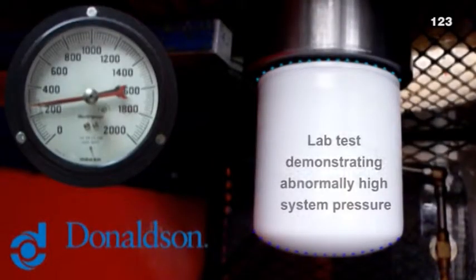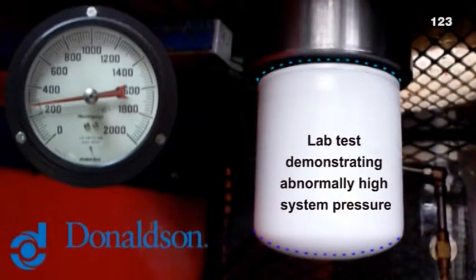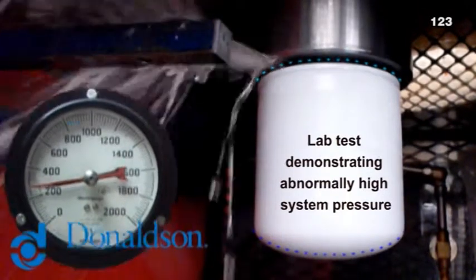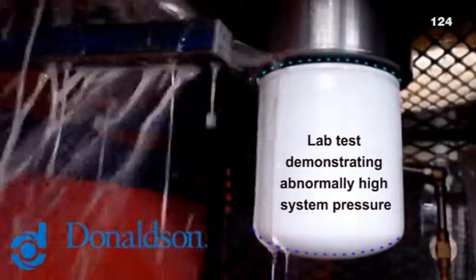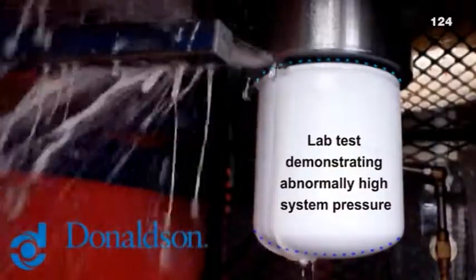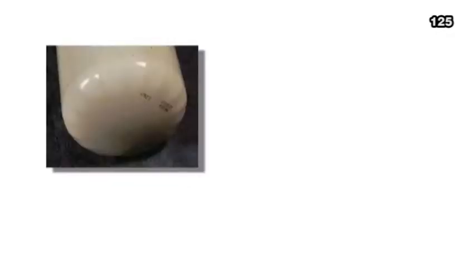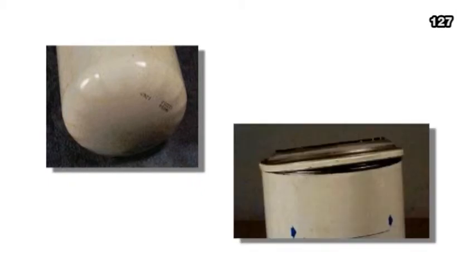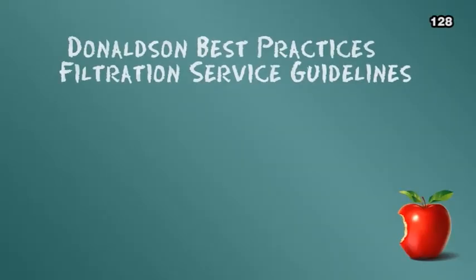As our closing illustration, we want to show you some things that can go wrong with a liquid filter when pressure in the hydraulic circuit goes far above normal. This may happen because of a fault in the system, such as a faulty pressure regulating valve. Note the domed appearance of this filter canister. A sure tell-tale sign that this filter is under abnormally great pressure. This inverted tap plate in the second photo is the result of the filter reaching burst pressure.